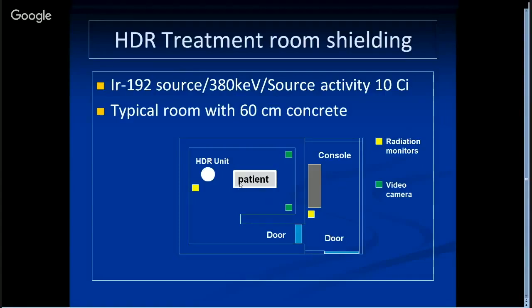Here is the room. We have the HDR unit and a couch for the patient. We are sitting here, that's the console, and here's the door, that's the maze. The yellow square, you can see that, those are radiation monitors — that's a requirement, you need one inside and one outside, indicating whether the radiation is on or off. We also have two video cameras inside, so you can monitor the patient or monitor the unit.